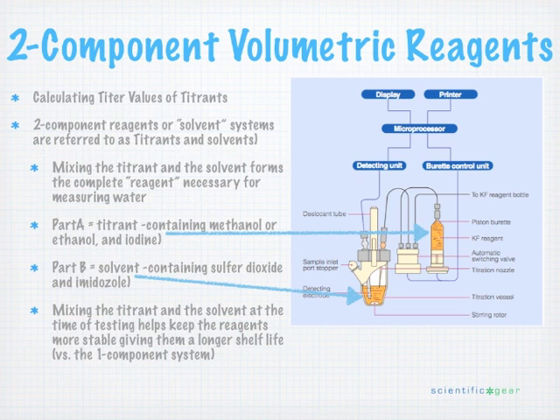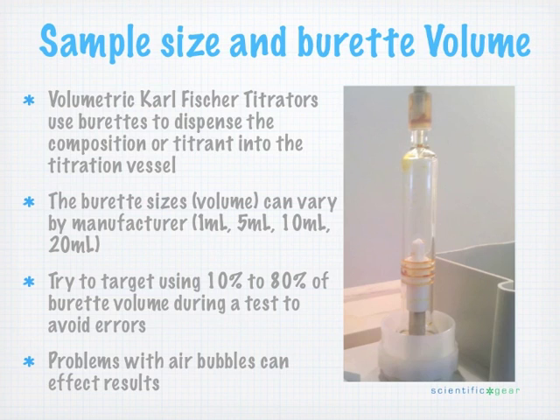Can we jump into sample size on the volumetric? With the volumetric system, we need to be concerned about sample size. The instrument manufacturers will tell us that for every titration we perform, we should design our analysis so that our sample consumes approximately 10% to 80% of whatever burette volume that instrument has. Our recommendation has always been to shoot for approximately 50%. If we've misjudged the water content of our sample or there's some variability, hopefully we'll always fall within that 10% to 80% window. We never want the instrument to use less than 10% because then it's out of the optimum operating range for the burette system.